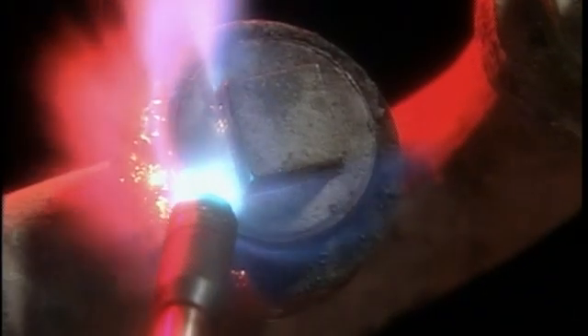Once you've turned on the torch, adjust the flame with the pressure regulator adjustment knob. Too much pressure can blow out the flame. Too little can cause improper combustion, and in some cases can cause the torch tip to heat up excessively. If this happens, it can present a potential danger to any combustible or meltable substance that it contacts. Many vinyl floors have been ruined this way.